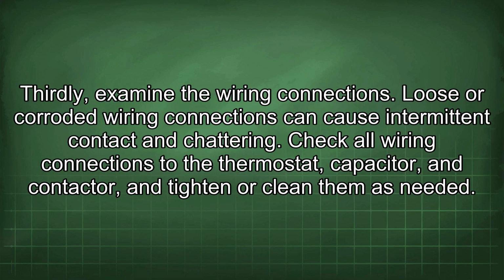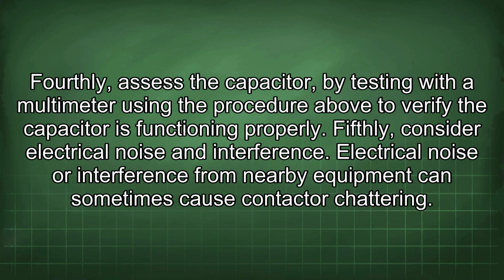Thirdly, examine the wiring connections. Loose or corroded wiring connections can cause intermittent contact and chattering. Check all wiring connections to the thermostat, capacitor, and contactor and tighten or clean them as needed. Fourthly, assess the capacitor by testing with a multimeter using the procedure above to verify the capacitor is functioning properly.